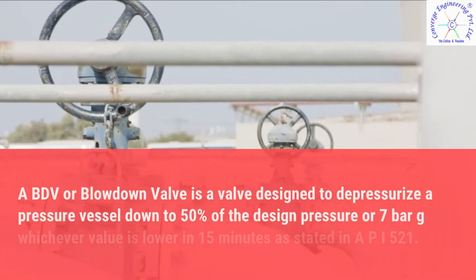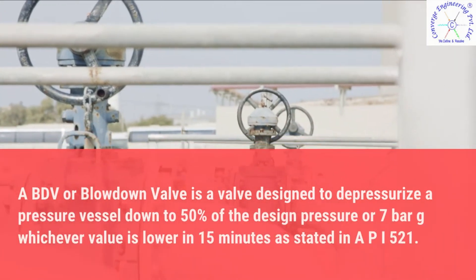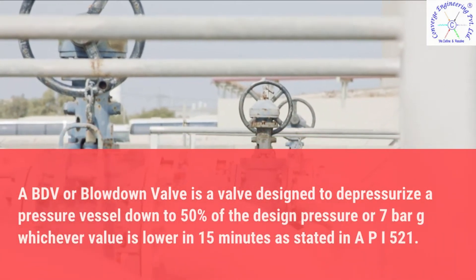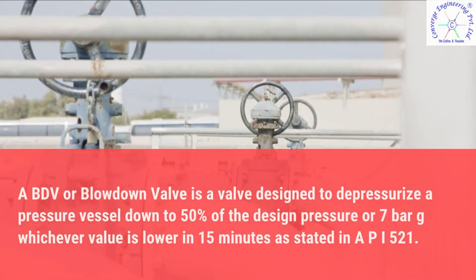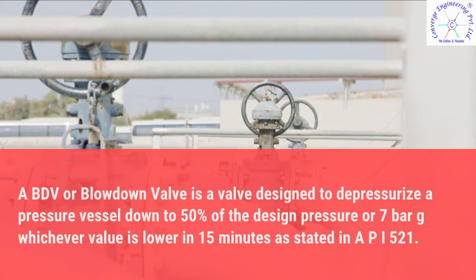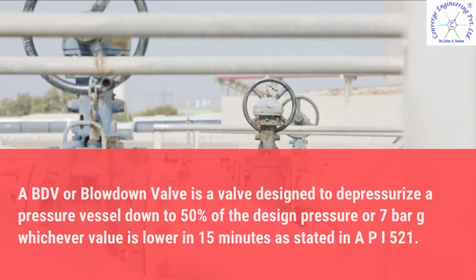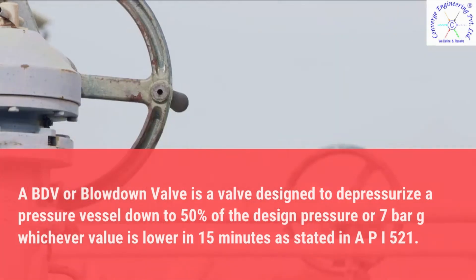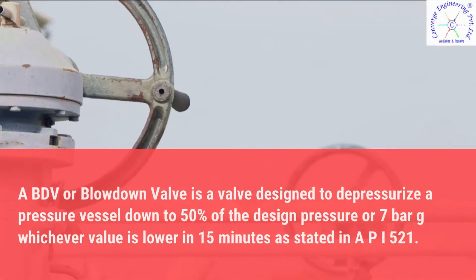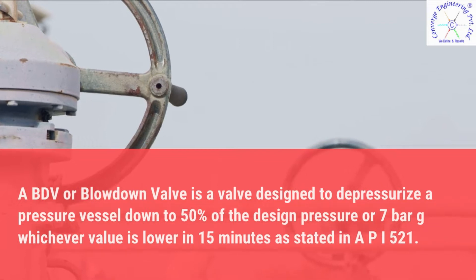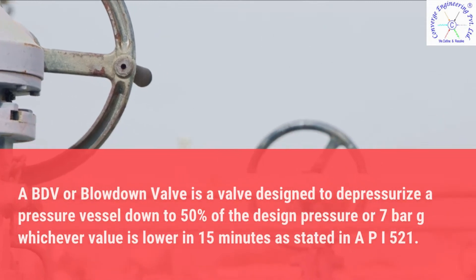A BDV, a blowdown valve, is a valve designed to depressurize a pressure vessel down to 50% of the design pressure or 7 bars G, whichever value is lower, in 15 minutes as stated in API 521.